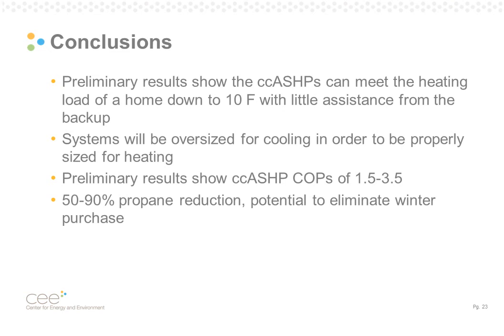Again, we are seeing some lower COPs for the unit at Site 3, which we're going to further investigate this coming heating season. And we are seeing a 50 to 90% propane reduction, which is really important because it has the potential to eliminate a winter purchase, since a lot of these homes have a 500-gallon propane tank. If you can reduce the amount of propane that the home has to use, then they could potentially purchase propane early in the season when it's less expensive and not have to refuel throughout the season.